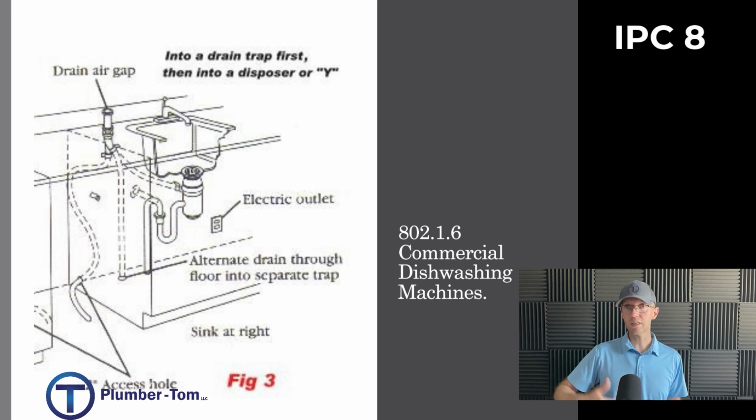Where I'm at in Utah, this is not required, and we're all glad for that because these are very problematic. They clog, they plug, they flood the top of the counter. People who have them generally don't like them. I personally haven't seen very many of these, but it does well fit within the code requirements because it is an air gap where it comes above the flood level rim and back down.